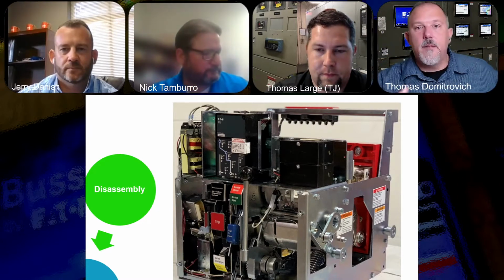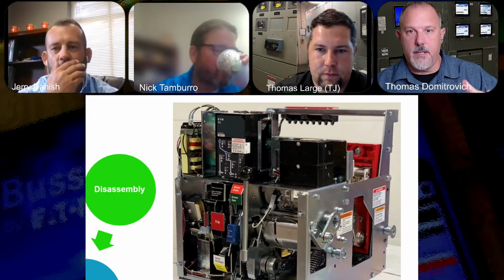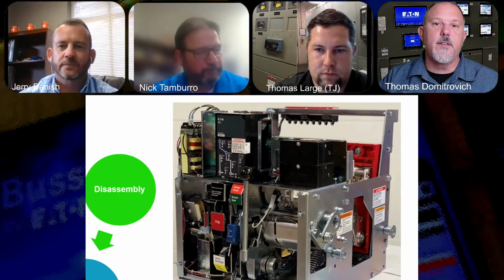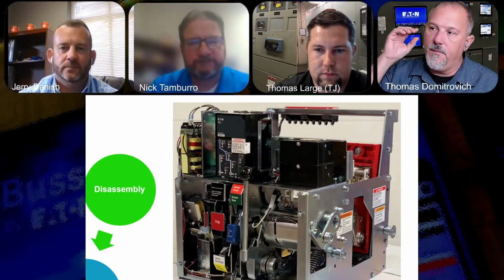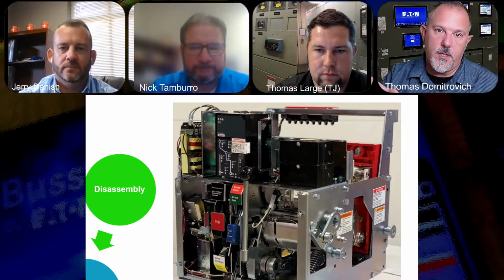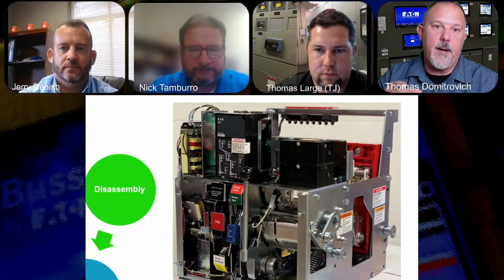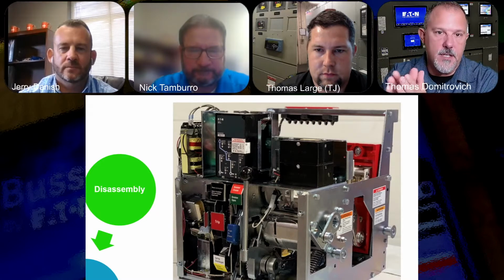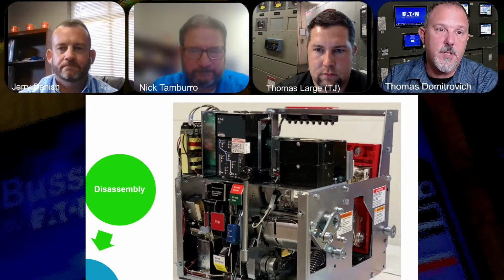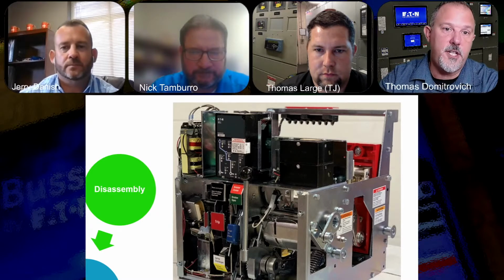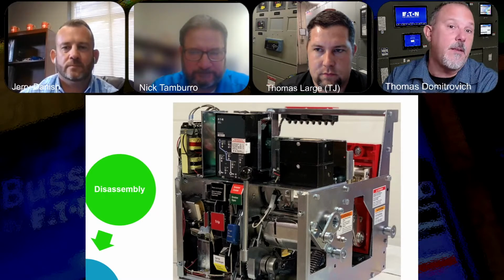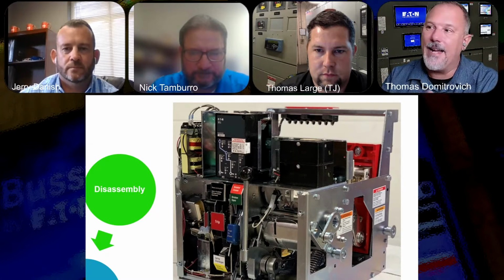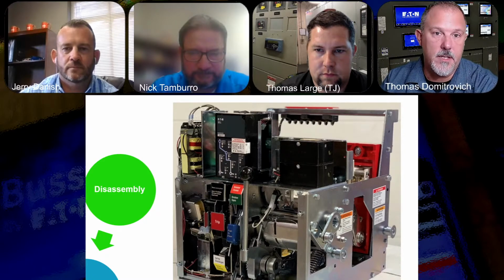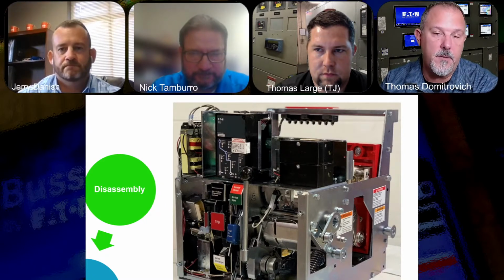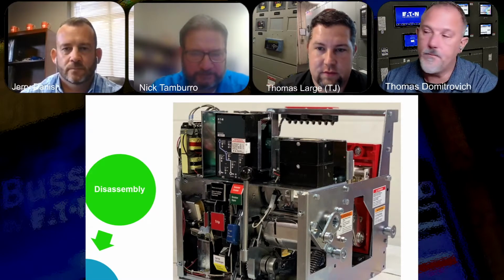So when you think about the performance within a system, say I have a coordinated or a selectively coordinated system, the flexibility of the new trip units will probably give me an advantage. Because of the tightness of the curves and because of the response times, I'll probably have a better chance of achieving a higher level of coordination because I can fit in between upstream and downstream devices. My point is, I'm not risking the performance of the system by doing this. I'm probably enhancing it from a reliability perspective in how they open.